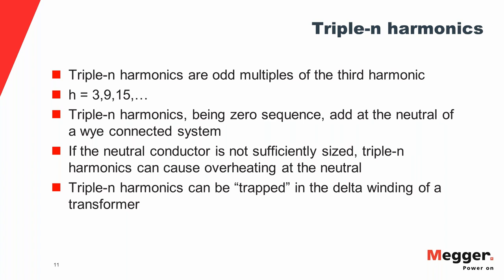Zero sequence or triple N harmonics can also be trapped in the delta winding of a transformer. One main application of the delta winding is to provide a circulating path for zero sequence currents. When zero sequence current flows in the system and encounters a grounded-Y delta transformer, it flows into the Y winding down to the neutral, but on the delta side it circulates within the delta winding and does not propagate further through the system.